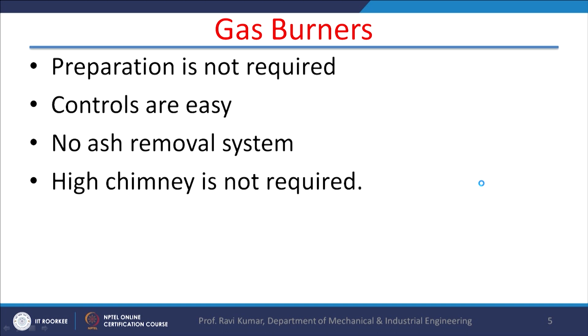Now, after oil burners, there are gas burners. Their application is limited, but the benefit is that preparation is not required, because gas itself is a volatile fluid available in gaseous form. Control is easy; we can easily control the flow of the gas, so when the heat requirement is less, we can turn the control valve and control the heat release rate. An ash removal system is not required, because gaseous fuel has no ash, and removing ash is a big job in a thermal power plant. Chimneys are also not required. So, these are the benefits of gas burners.